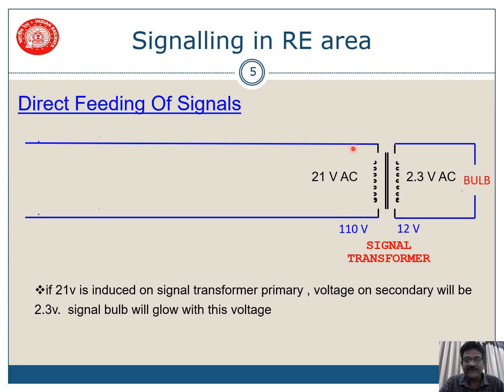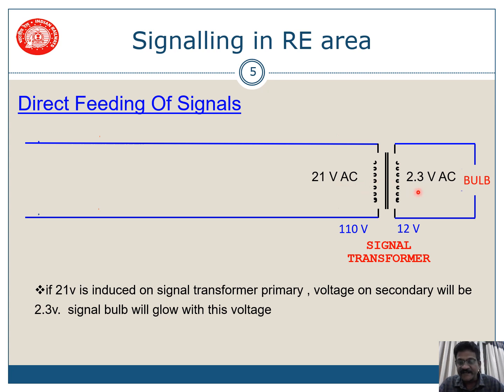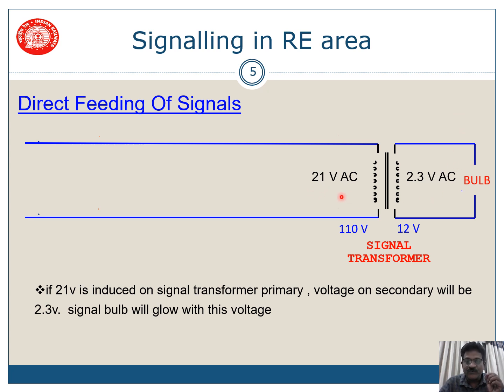In direct feeding of signals, if 110 volts is given the output will be 12 volts. But if the input is 21 volts AC from some foreign feed, then 2.3 volts is the secondary output and the bulb will glow. The ECR may not pick up, but the bulb will glow which is unsafe. Hence our signaling system shall be such that the voltage on the primary side shall be less than 21 volts.